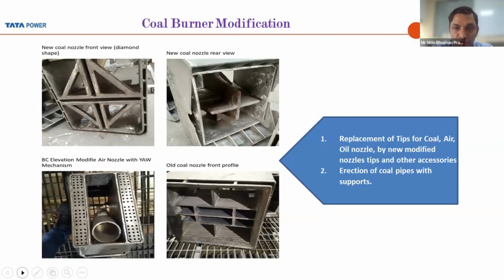Basically, post installation, the trials are going on, and at full load condition, when this NOx system was introduced, we faced many problems in the beginning. In the startup condition, the furnace pressure while taking the oil gun normally goes to 25 mmWc, but at the start it went up to 75 mmWc in a single gun. But with every trial, we are in consultation with GE, and they are trying to reduce these issues. Physically, the fireball seems to have shifted upward, as the intensity of the flame is showing low in the lower elevation.